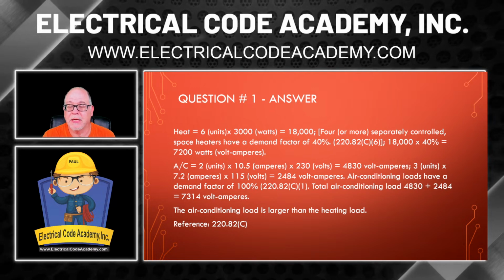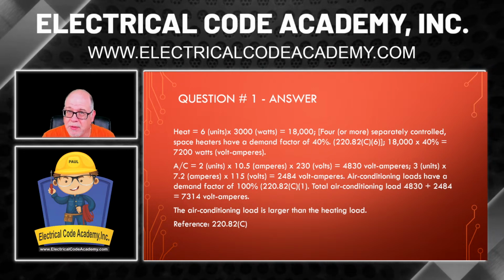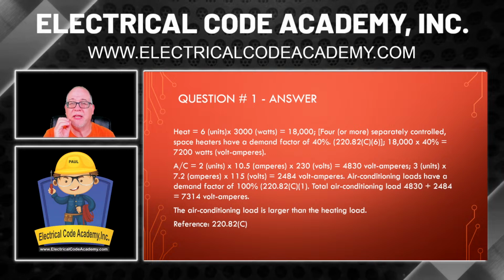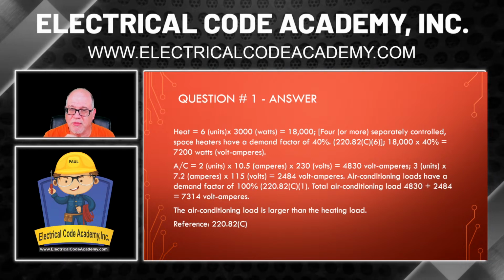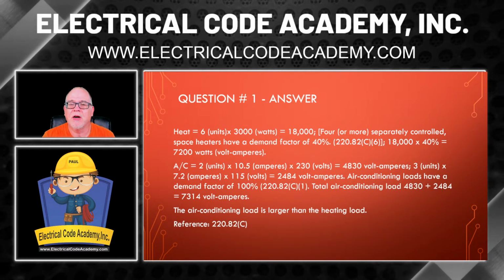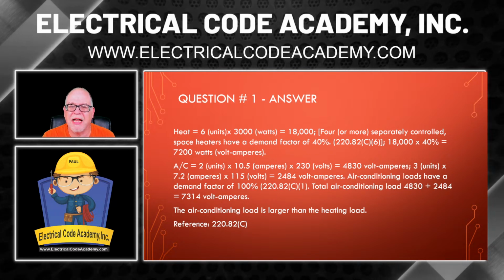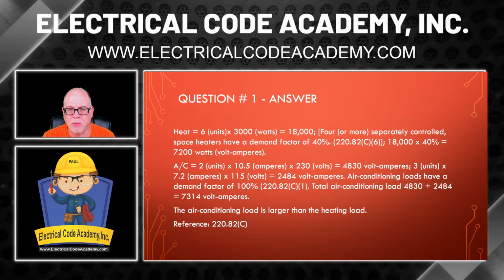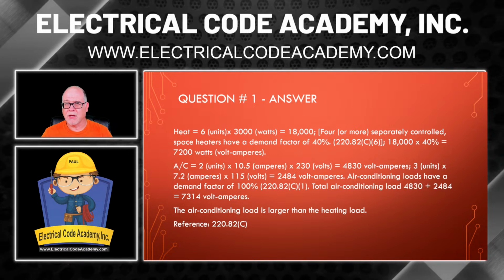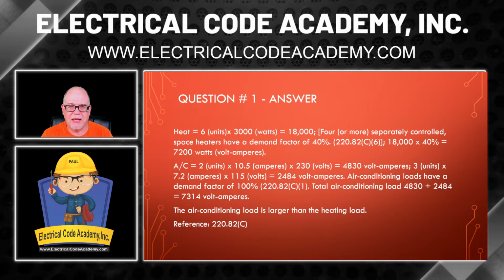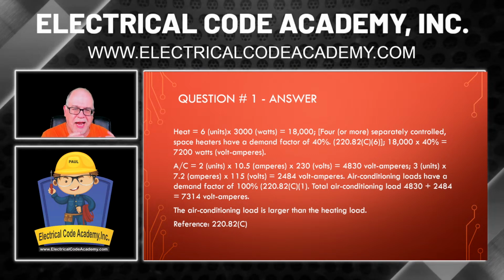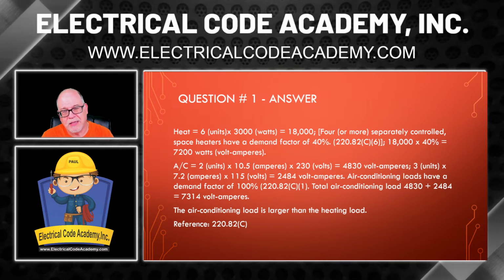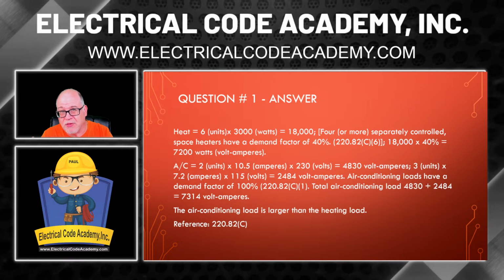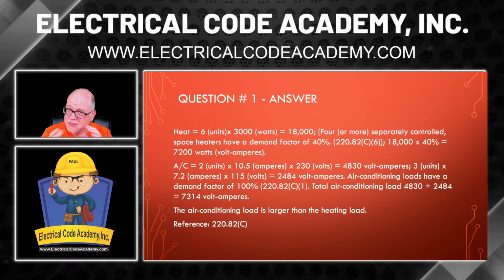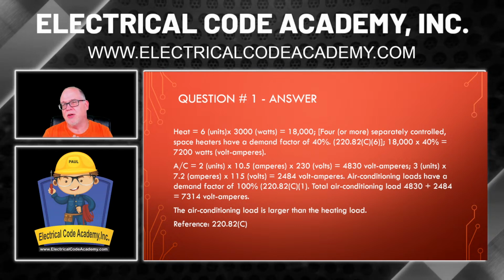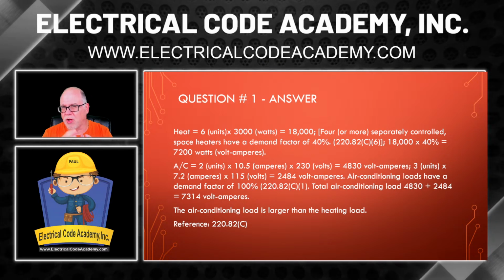Okay? Now let's do the 3 7.2 amp air conditioning units. That would be 3 times 7.2 times 115 volts. That is 2,484 volt-amperes. Remember Ohm's law: in order to find VA, it's synonymous. We're just going amps times volts equals watts, and watts is synonymous with VA. See how that works?